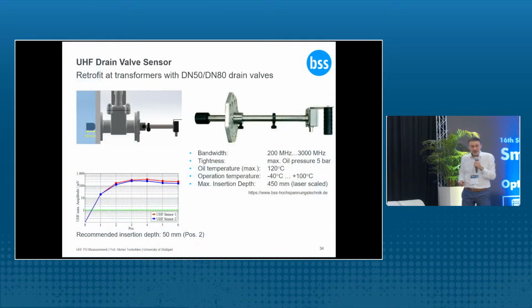There are two types of sensors. These are so-called drain valve sensors, because you can install these sensors at drain valves which are installed at the transformer tank to release the oil. So you can retrofit these sensors. Yeah, they are installed here at the valve. Then you open the valve, and then you can push in the antenna here inside the tank.